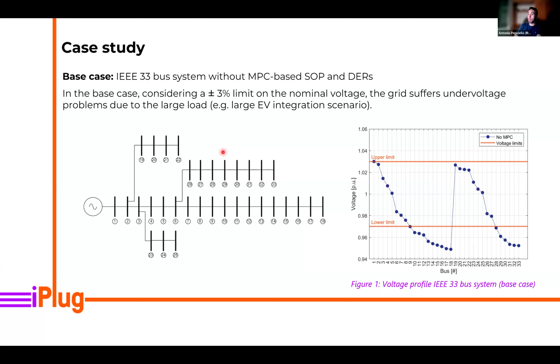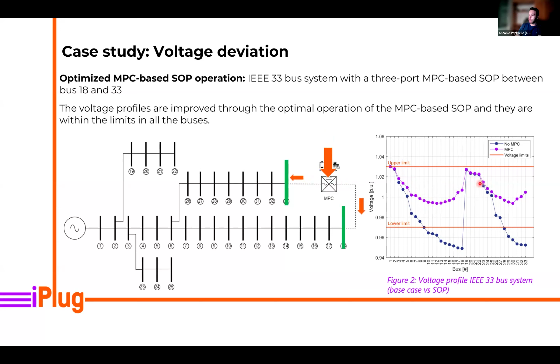In this case, we have a 3-port soft open point. It's connected to 2 buses, bus 33 and 18, and the third port is connected to distributed energy resources, in this case, flexible ones. From the figure on the right, you can see how by optimizing the active and reactive power flows provided by these ports connected to the feeders of this soft open point, we can significantly improve the voltage deviations in all the buses of this IEEE 33 bus system. So the purple curve is the one with the optimized soft open point, whereas the other one was the benchmark case.